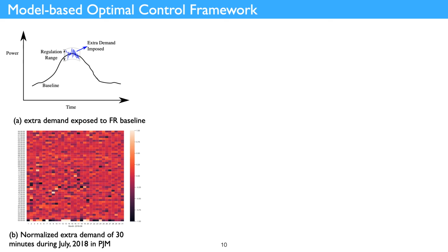So previously we talked about the frequency regulation control, where we enable the data center to track a fast changing power signal. In this section, we're going to talk about a model-based optimal control framework that helps to minimize the operational cost of the data center during the provision of frequency regulation and participating in the energy market. Before I go to the detailed formulation of the optimization problem, I want to introduce a fact. We know that when we're providing frequency regulation, the regulation signal over a long time is usually considered energy neutral. But when we calculate the energy of the regulation signal in a short time, for example, 5 minutes, 10 minutes, or even 30 minutes, it's not always energy neutral.